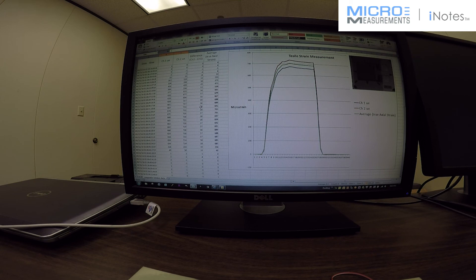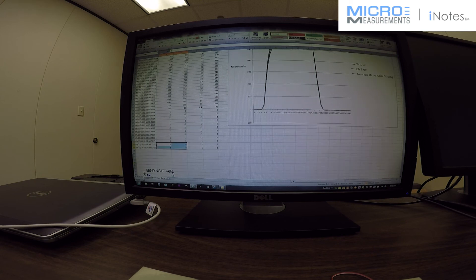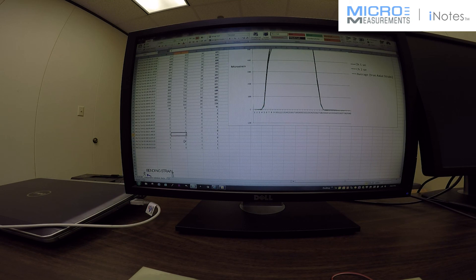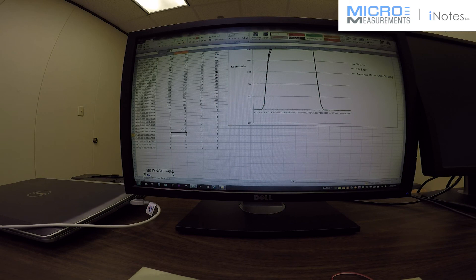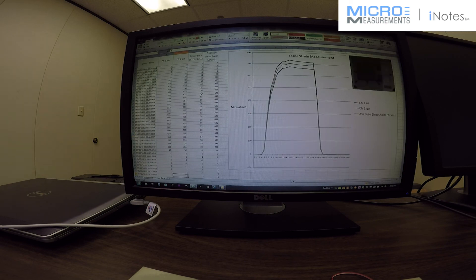Now what I would look for if I were to question this is if one or both of the gauges did not return to zero and maybe indicated, you know, greater than twenty or more microstrain, I would really question if the gauge was installed correctly and would probably want to reinstall a gauge and run this test again. Thank you for the time and I hope this is helpful.